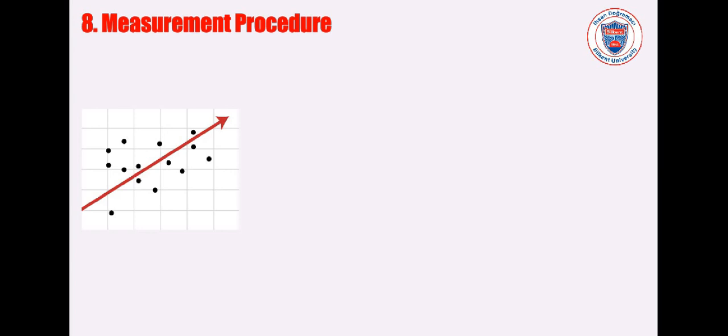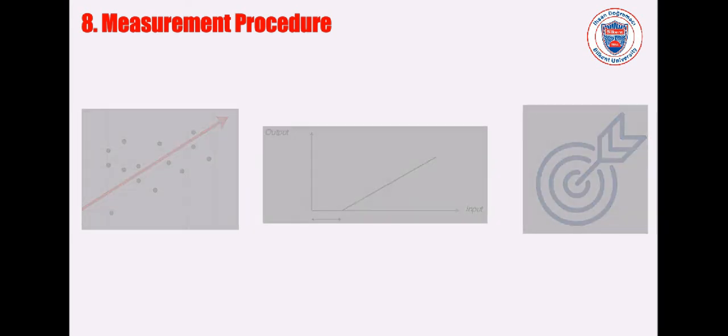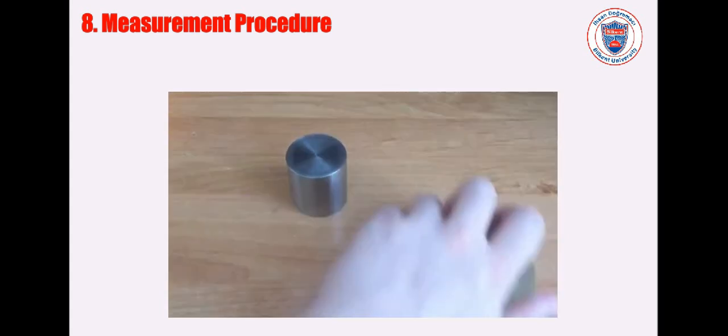After the calibration steps, the instrument now has little to no linearity errors, its threshold value is known, and the precision information is known, which makes it possible to accurately define the uncertainty of measurements. The mass measurement procedure is as follows. First, prepare the test load and a reference load.